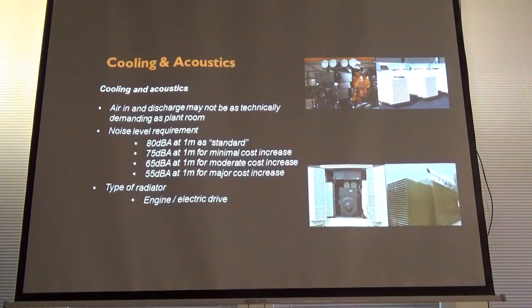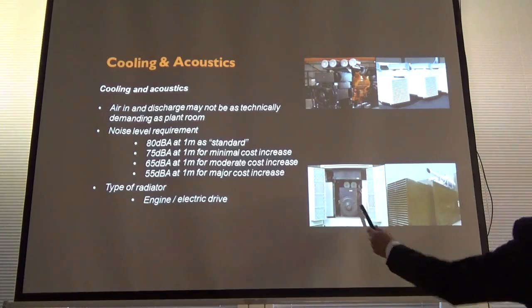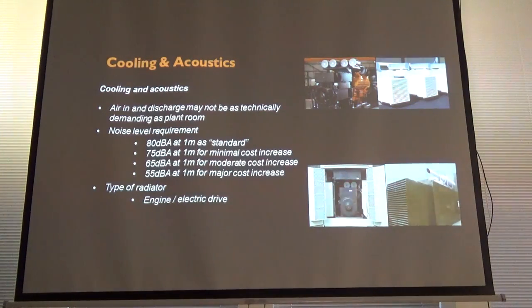There you go, that's the unit, bottom, that one there. It's shoehorned in, tight as anything, uses all the back pressure on a box silencer on a roof, but it's a very good, portable unit. But the actual power requirement on a lot of the sites will probably be only 100, 150 kVA. So that unit's running well under its normal limits, because normally when a set's running, you don't want it sustained running at less than 30% of its rating, because it causes carbon build up, and it causes fuel to pass through into the lube oil. It's not good.